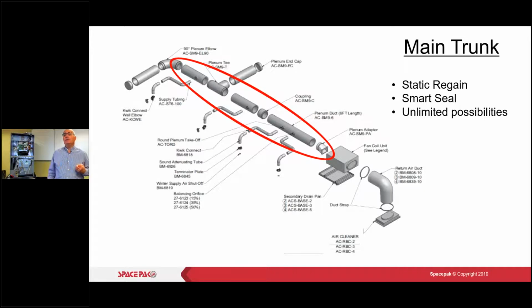And here's where you want to be the most profitable, gentlemen: you want to run the most plenum that you can. The more plenum that I run to get as close as I can to the rooms before my drops is going to save you time. It's going to save you money. And a lot of my SpacePak installers will pre-drill, prefab their plenum outside before they bring it in. So they'll drill their holes outside before they add their 2-inch outlets. So they've planned it out, they've sketched it out, they know what they're going to do. And when they bring that plenum into the attic space, it's a much faster install.